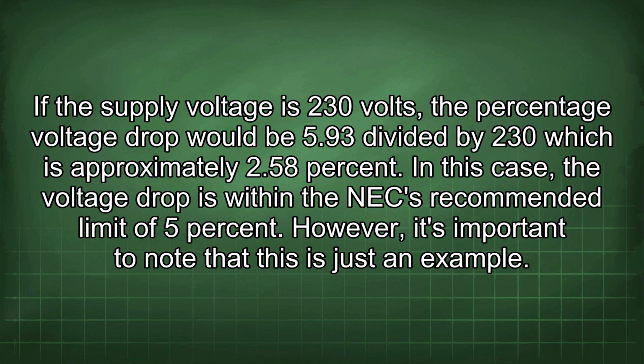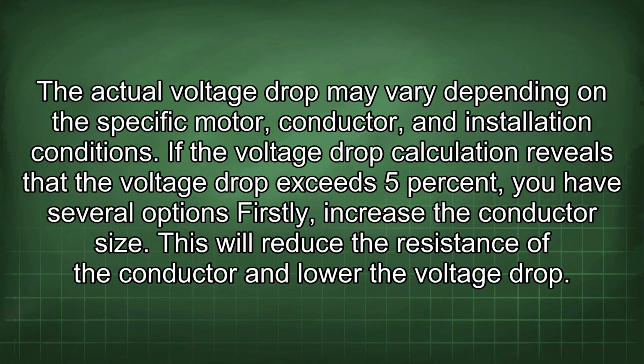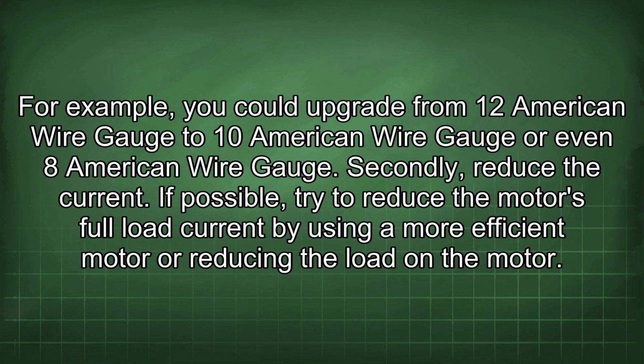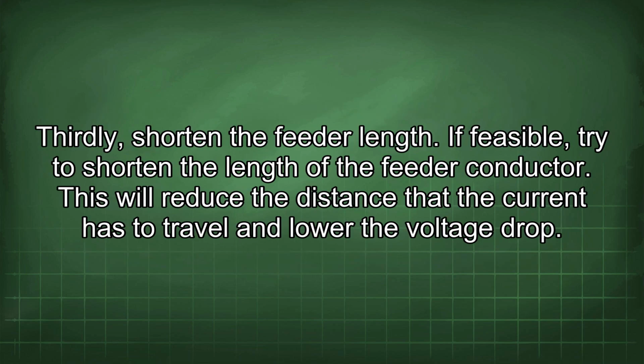However, it's important to note that this is just an example. The actual voltage drop may vary depending on the specific motor, conductor, and installation conditions. If the voltage drop calculation reveals that the voltage drop exceeds 5%, you have several options. Firstly, increase the conductor size. This will reduce the resistance of the conductor and lower the voltage drop. For example, you could upgrade from 12 American wire gauge to 10 American wire gauge, or even 8 American wire gauge. Secondly, reduce the current. If possible, try to reduce the motor's full load current by using a more efficient motor or reducing the load on the motor.